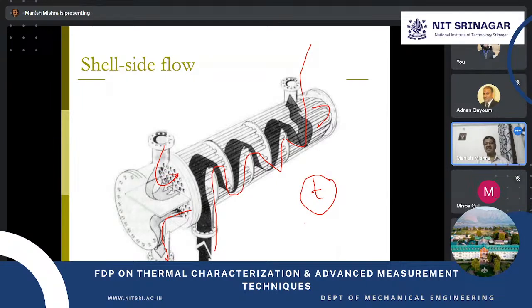So one additional parameter that comes into picture is residence time — the time the fluid spends inside the exchanger. If we can increase that for the same heat transfer area and surface area density, the effective heat transfer will be more and the effectiveness of the exchanger will also increase. This is another objective we always target for the same exchanger, and that's the reason we provide a number of baffles.